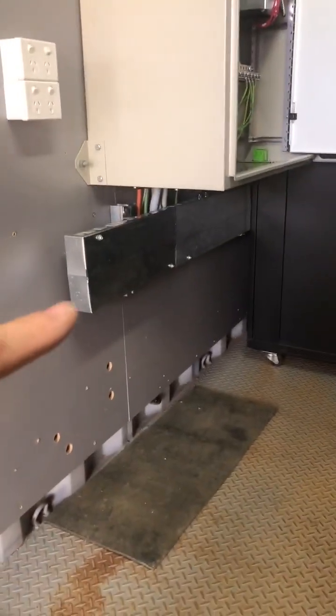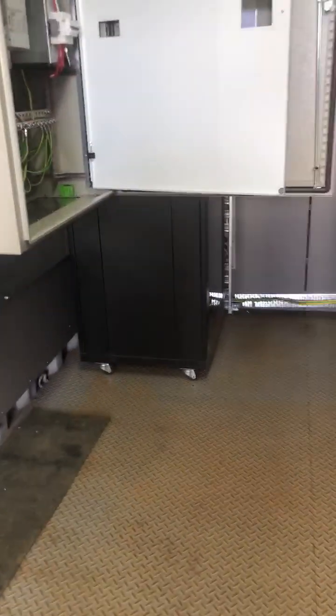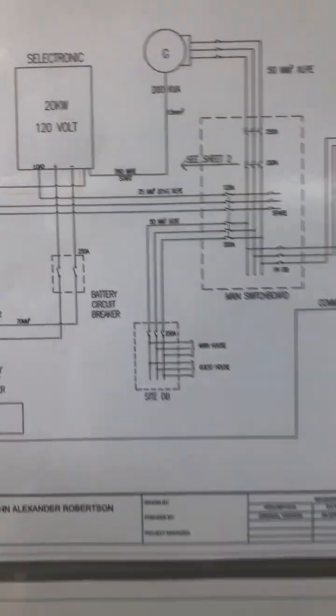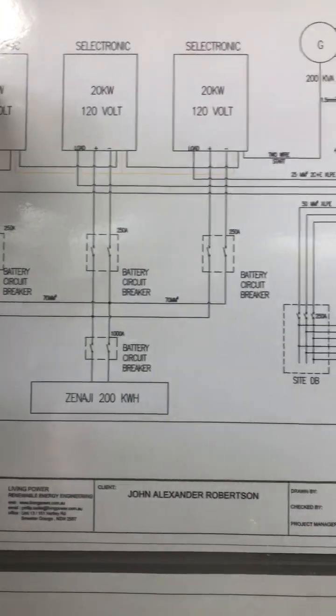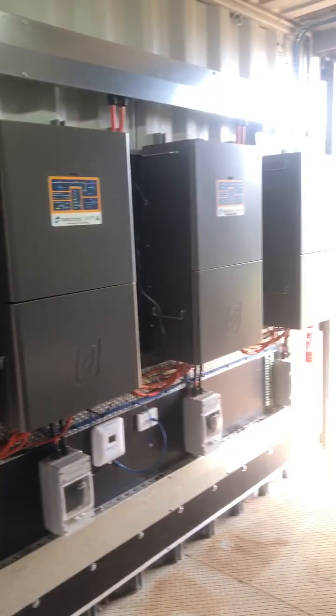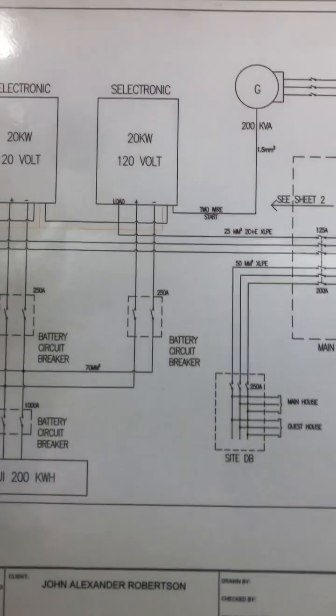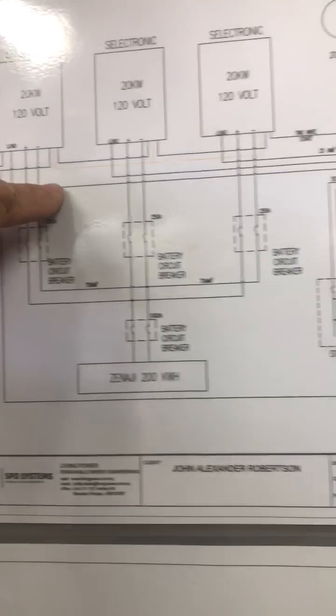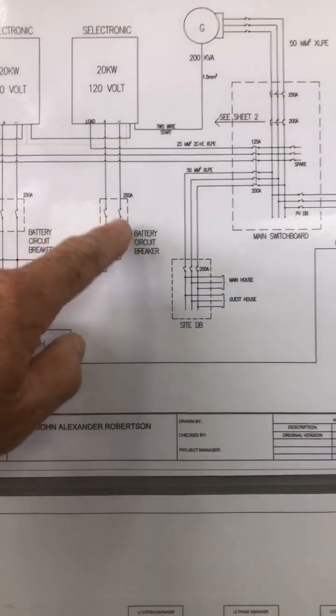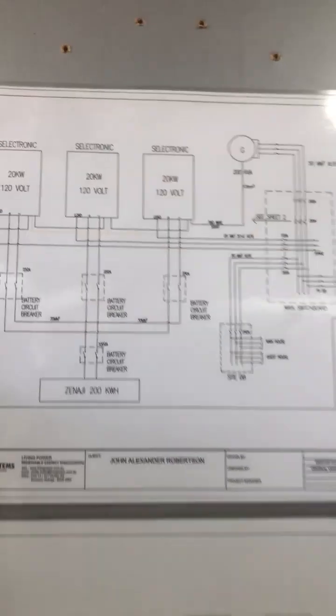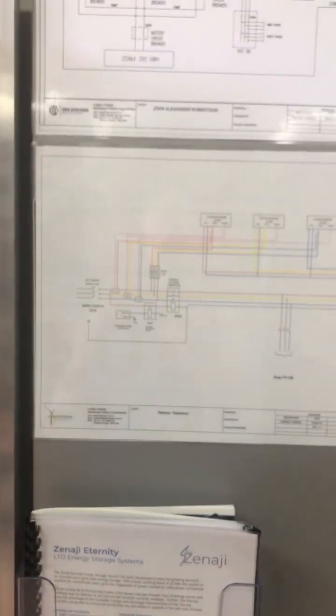We've got our generator cables coming into the main switchboard, which I showed you a minute ago. They're actually underneath here and going into the generator room behind us. And there's our Selectronic 20 kilowatt inverters, those inverters there. There they are, and if you trace their cables out, they also come over into the main distribution board there. There's their isolators under each of the Selectronic inverters.